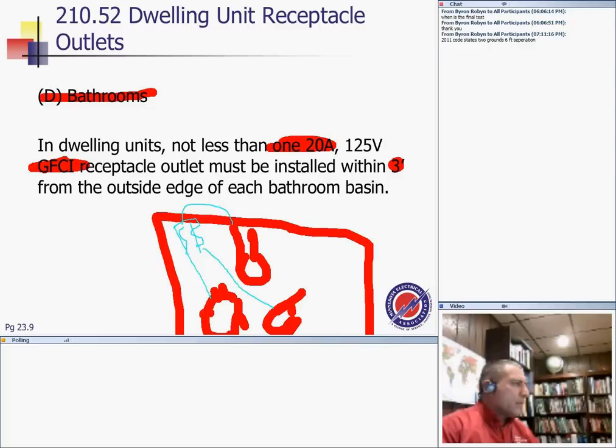And for the receptacle, I went all the way to a 20 amp circuit. Okay? All my wires are number 12. This is a GFCI receptacle. Is the installation right? Can I do that, guys? Can I bring a 20 amp circuit, feed the receptacle and the fan and the light?